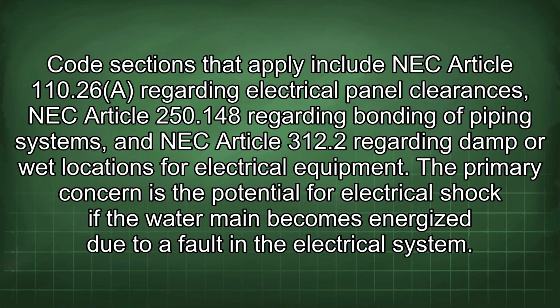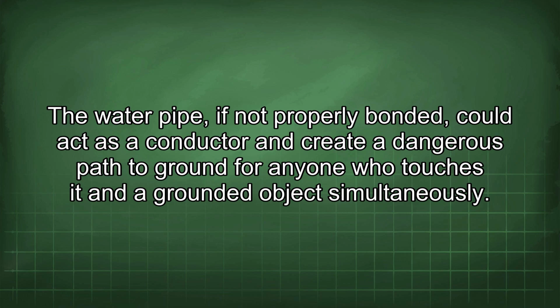Code sections that apply include NEC Article 110.26 regarding electrical panel clearances, NEC Article 250.148 regarding bonding of piping systems, and NEC Article 312.2 regarding damp or wet locations for electrical equipment. The primary concern is the potential for electrical shock if the water main becomes energized due to a fault in the electrical system. The water pipe, if not properly bonded, could act as a conductor and create a dangerous path to ground for anyone who touches it and a grounded object simultaneously.